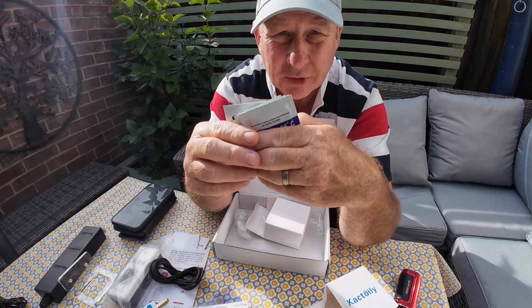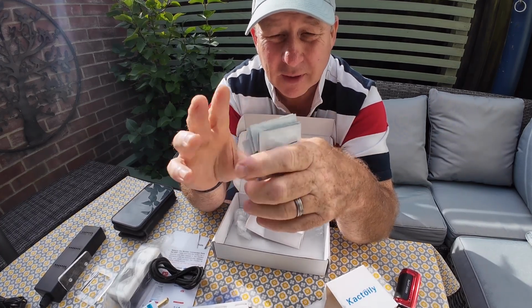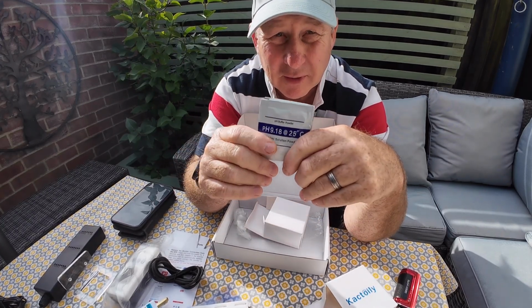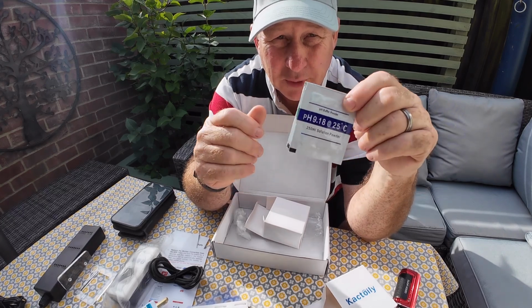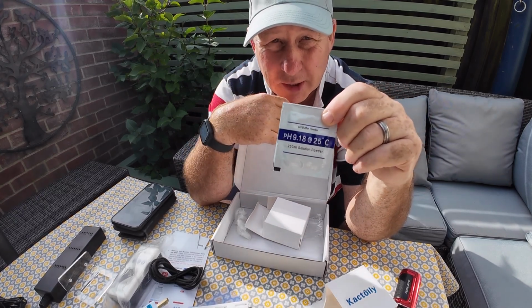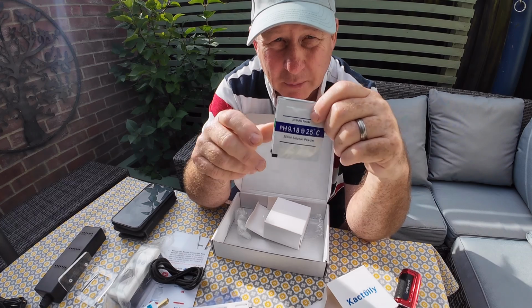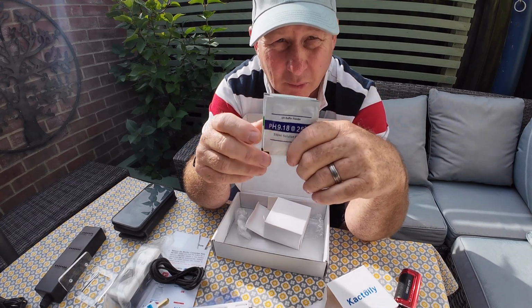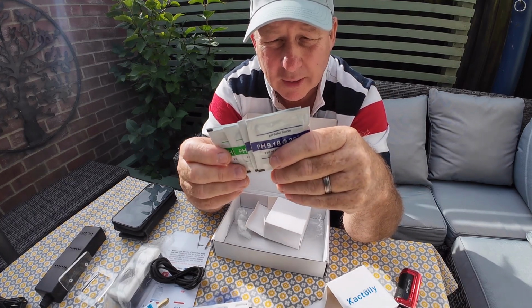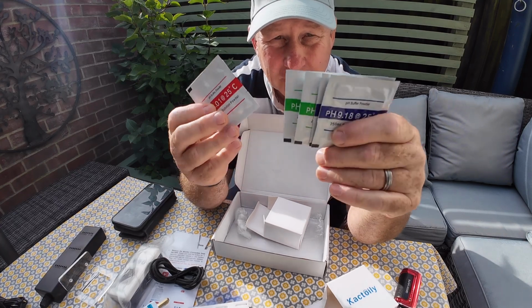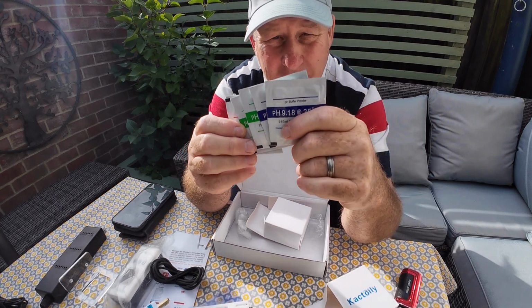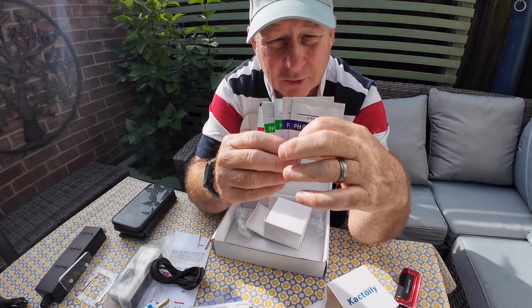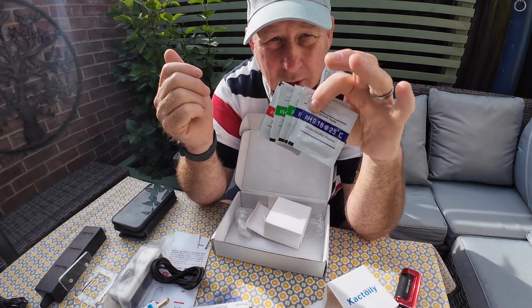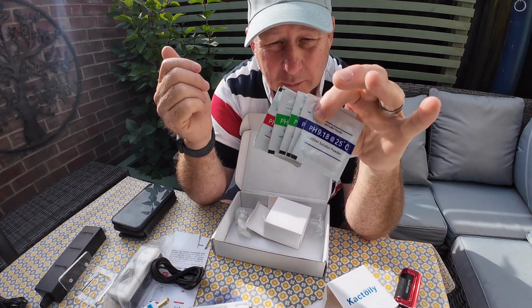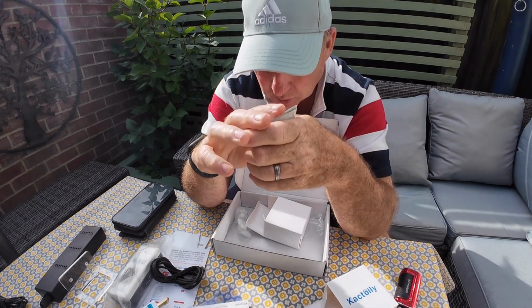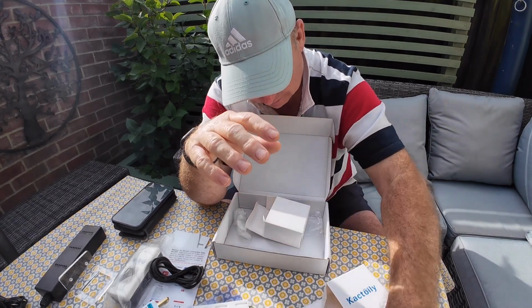Now, the reason you get 3 different sachets is that KACTOILY realised that by doing a 3-point calibration rather than a 2-point calibration when you calibrate your pH probe, it's a lot more accurate, and it will hence give you a better reading. You don't have to do a 3-point, you can do a 2-point, but KACTOILY recommend doing a 3-point calibration so you can get a lot more accurate readings and a lot more accurate calibration, which is spot on. I've not seen that before, so put those over there.